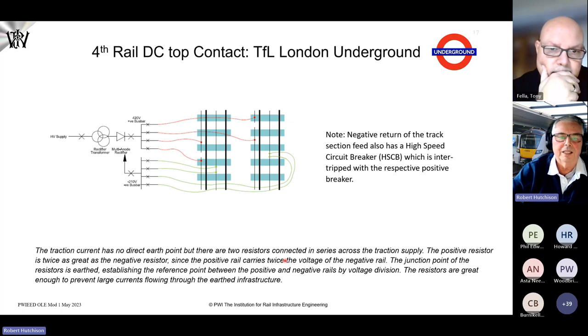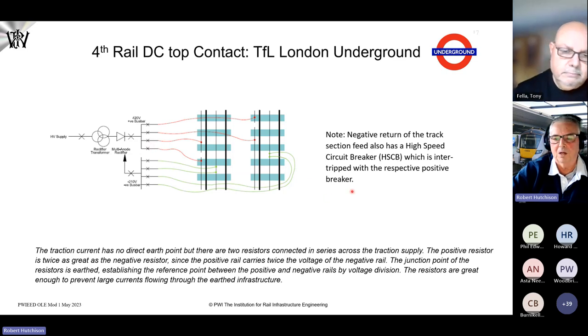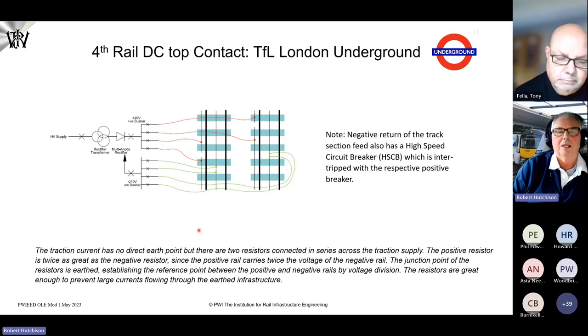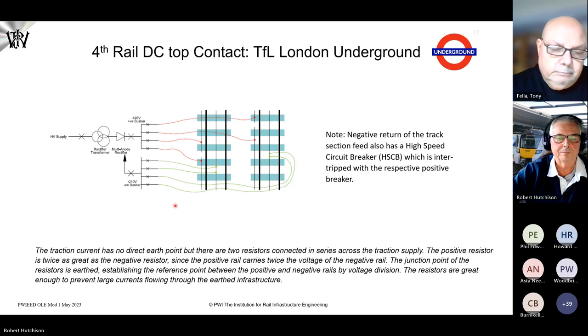London Underground is fourth rail. Interestingly, the DC is also switched or has circuit breakers on it, with two inter-tripping circuit breaker panels providing a similar voltage, though they split the voltage with reference to earth slightly differently. Also on London Underground, they can put bleed resistors on so they can measure leakage to earth and monitor it, to reduce and sort out any problems with stray current. That's specifically unique to London Underground.